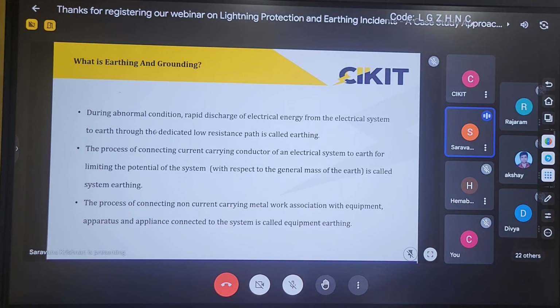So for one of the projects, the consultant mentioned a 50/6 copper strip for the particular transformer earthing, but what they did was, since the conductor sizing is the same, they replaced this 50/6 copper strip with a 50/6 GI strip. So the conductor cross-sectional area is the same. So they mentioned that we have provided the same area. But what is the parameter which makes a difference? Let us consider the difference in the current carrying capacity.